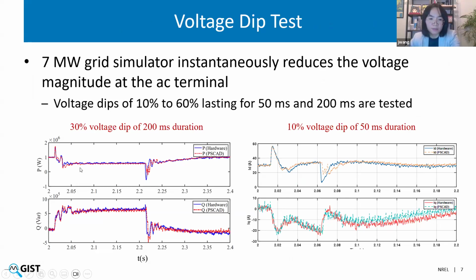The PSCAD results align with the hardware inverter really well. Even in the transient moments, you can see here they match pretty well. And when the dip is removed, the post-fault behavior also matches pretty well. So this is for the 30% voltage dip. And we also have a 10% voltage dip. You can see the PSCAD results match the hardware results pretty well as well. So this is one example testing result.